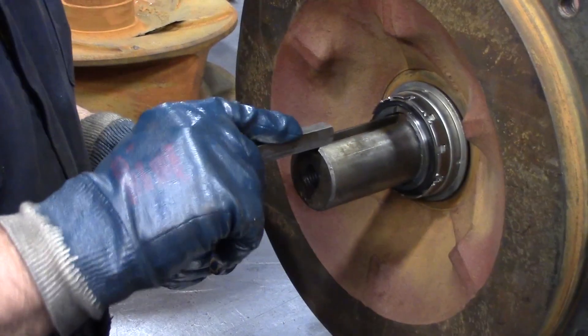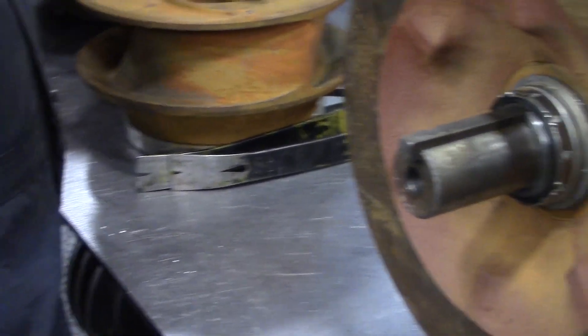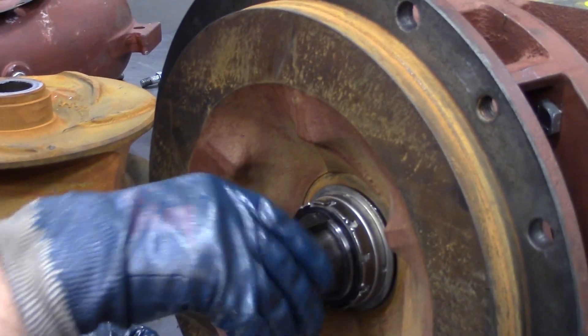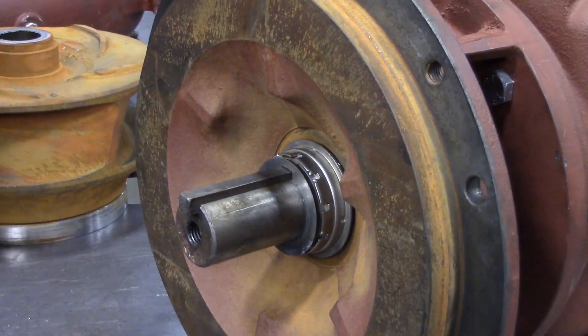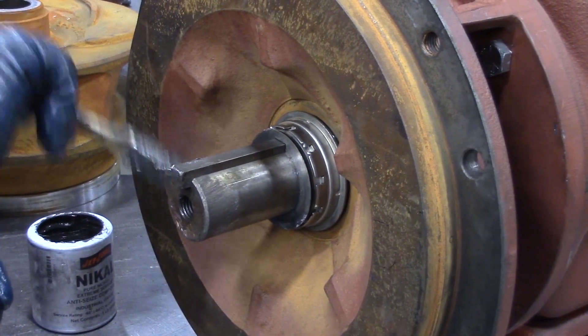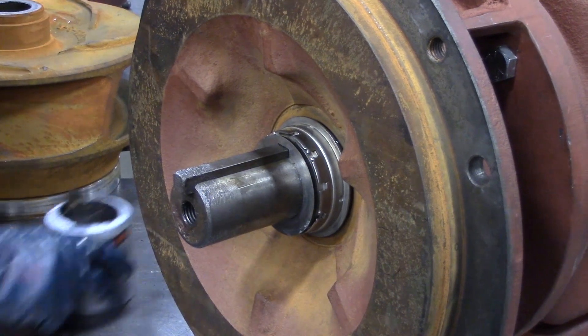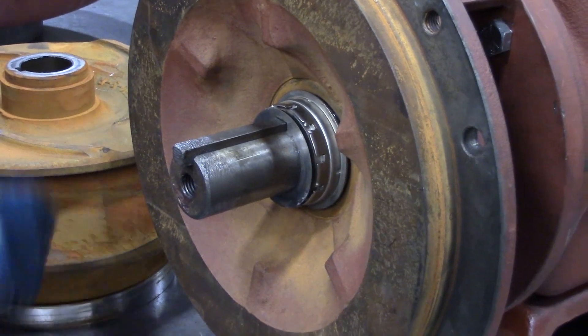Now that the seal's in, we're going to start putting the impeller back on. Make sure you put your key in and then replace any shims that were there before you put your impeller on — use the same amount of shims that came off so you get the right back vane clearance. Kenny's putting some anti-seize on the shaft to help the impeller slide on easier. At this point, you want to put your spring on.